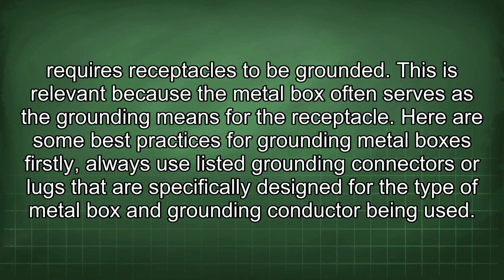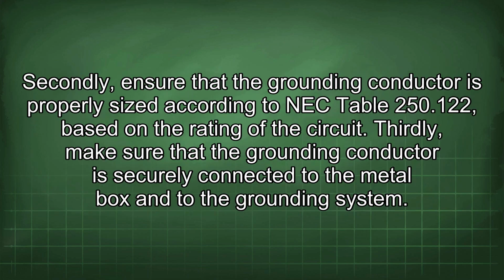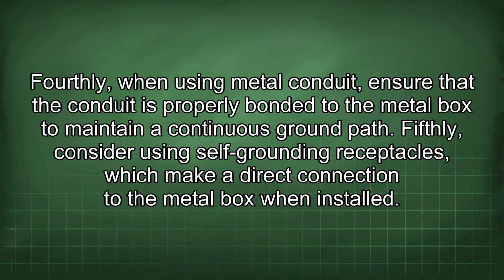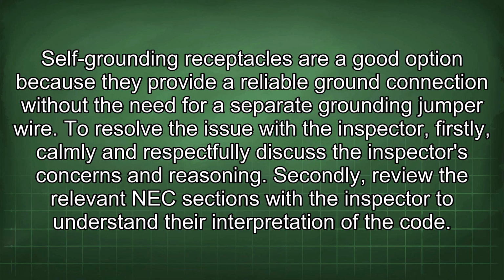Here are some best practices for grounding metal boxes. Firstly, always use listed grounding connectors or lugs that are specifically designed for the type of metal box and grounding conductor being used. Secondly, ensure that the grounding conductor is properly sized according to NEC Table 250.122, based on the rating of the circuit. Thirdly, make sure that the grounding conductor is securely connected to the metal box and to the grounding system. Fourthly, when using metal conduit, ensure that the conduit is properly bonded to the metal box to maintain a continuous ground path. Fifthly, consider using self-grounding receptacles, which make a direct connection to the metal box when installed. Self-grounding receptacles are a good option because they provide a reliable ground connection without the need for a separate grounding jumper wire.